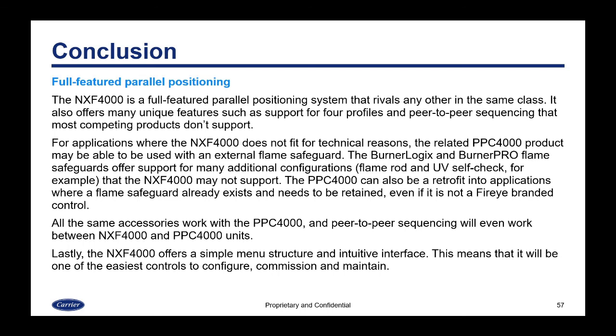So I did have one question, and then I'll take any other questions if you want to put them in the chat. What is the 60-3005 terminal block kit? This is a recent development, and you should be getting information from your RSMs about this soon. The terminal blocks on the NXF4000 and PPC4000 up until now have been shipped with the control, but they're becoming a separate part. So the control's price will be decreased accordingly, and the terminal blocks will be available separately. So you'll now order a control, and you'll order a terminal block kit separately. That terminal block kit is the 60-3005. And the VFD card will now come with the terminal block for the VFDs separately. So there was a small change, and you should be getting information from your RSMs about that.